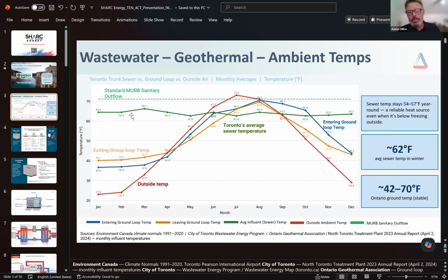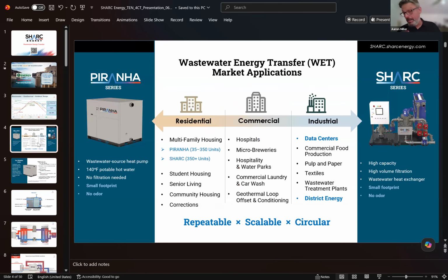Whereas you look at that sewer temperature, 60 some odd degrees year round, super consistent temperature. So I've got constant flow and constant temp. That's a dream condition for heat pumps. You've got now a condenser water loop with just all year round just running energy. So now the question is, how do you harvest the energy out of that? Otherwise, the water that you wouldn't want to touch, right? We have two boxes, now three technically, and it all comes down to scale. Piranha and the SHARC, right?